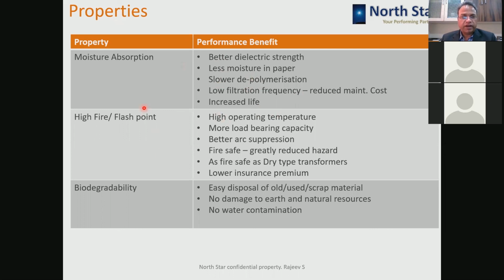Okay. Now high fire and flash point. Because the ester will catch fire only at a higher temperature, you can operate the transformers at elevated temperatures. You need not worry about the 105 degrees centigrade limit. You can go to higher temperatures very safely, at least up to 120 degrees centigrade or even 130 degrees centigrade. So you can use the transformer on higher loads, because as the load increases, the temperature increases.